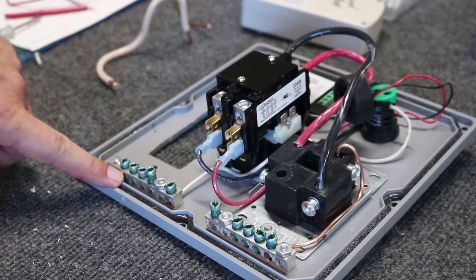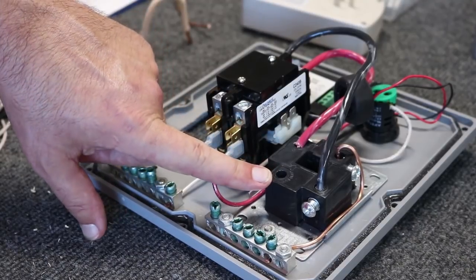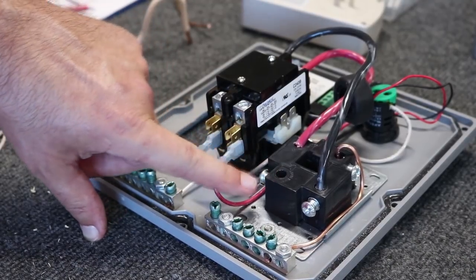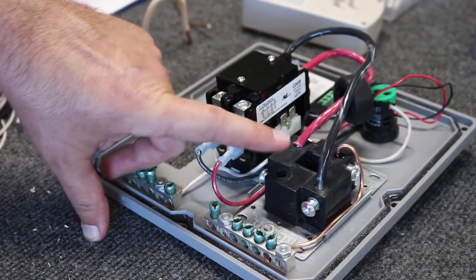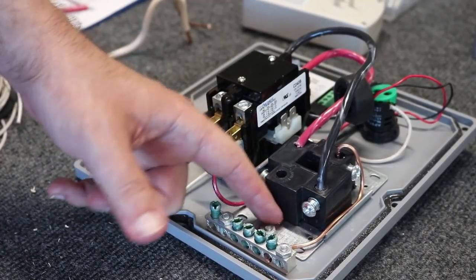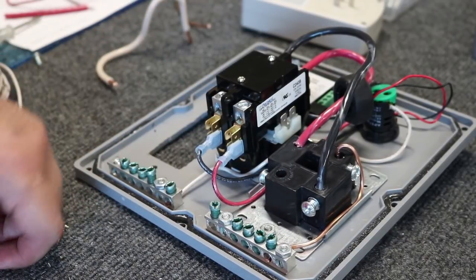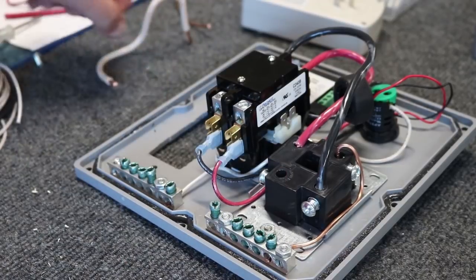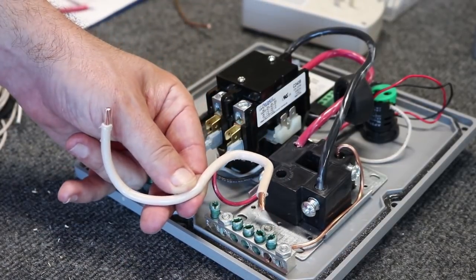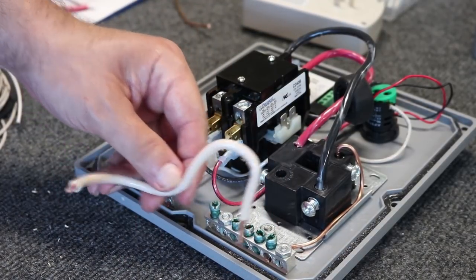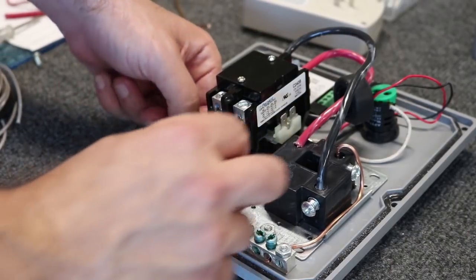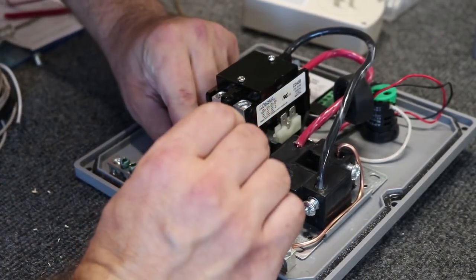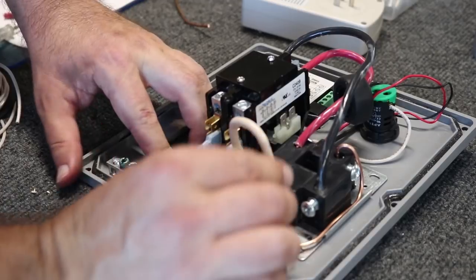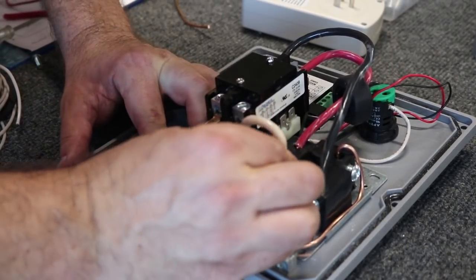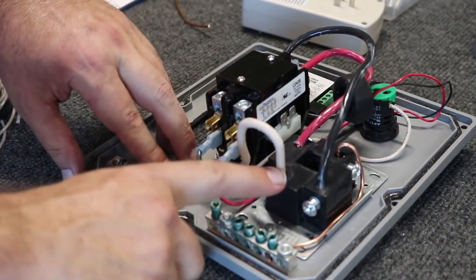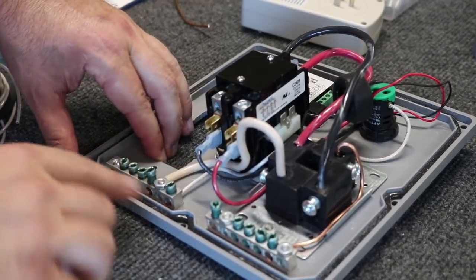Now that I've got the neutral bus, I can connect the neutral on the NEMA 14-50. Even though an EVSE at 240 volts does not use the neutral, I might repurpose this for something else, so if I do, I want to have the neutral on there. I already cut a piece of heavy 6 gauge wire and bent it. I'm going to get it through down here to the neutral bus, and then up here to that connection in the NEMA 14-50, and then tighten both of those down.